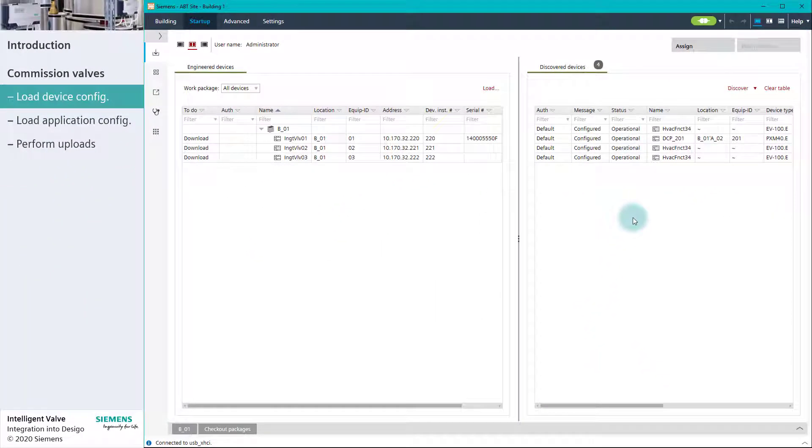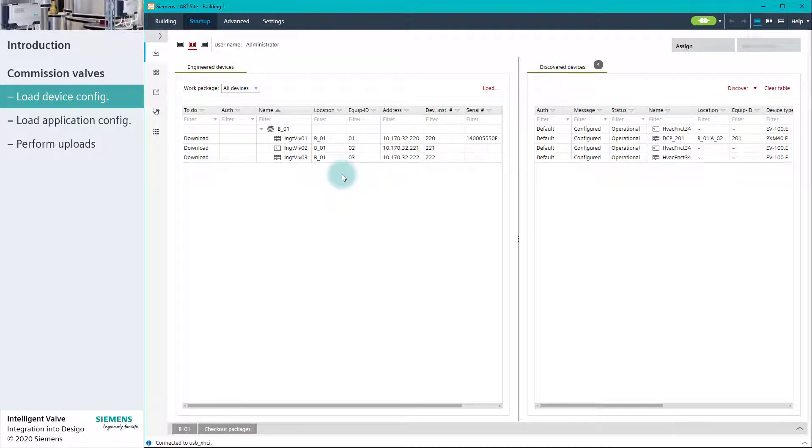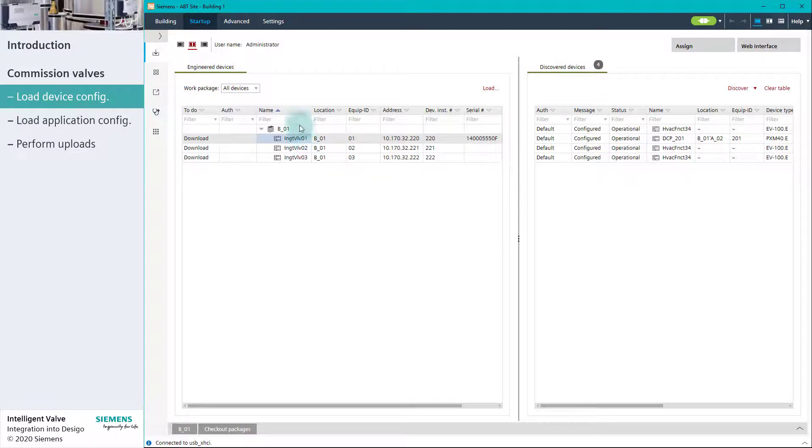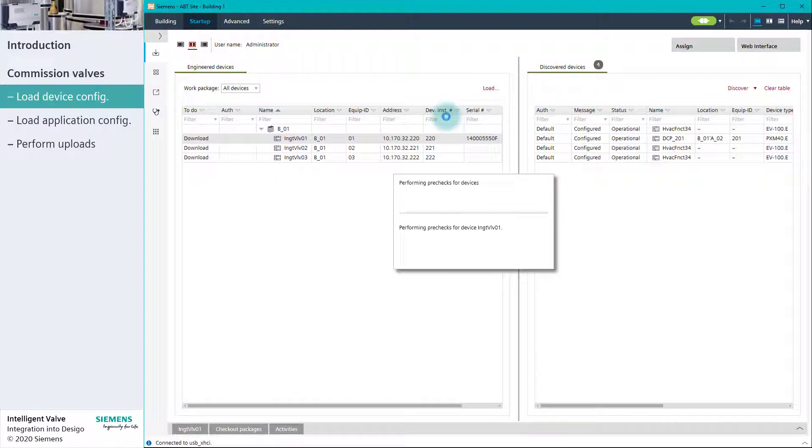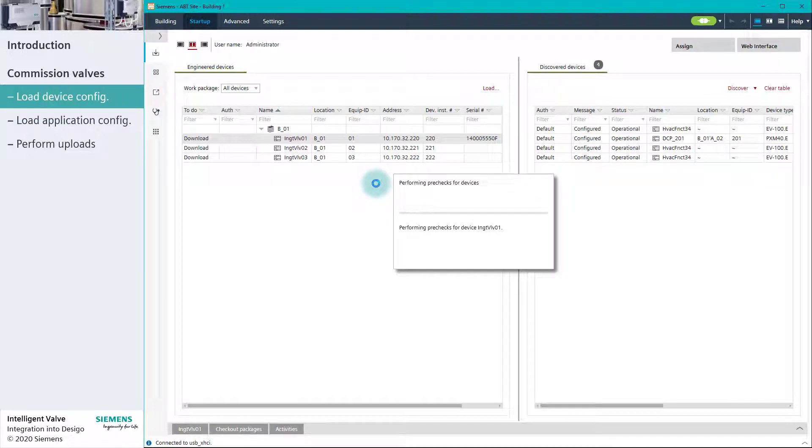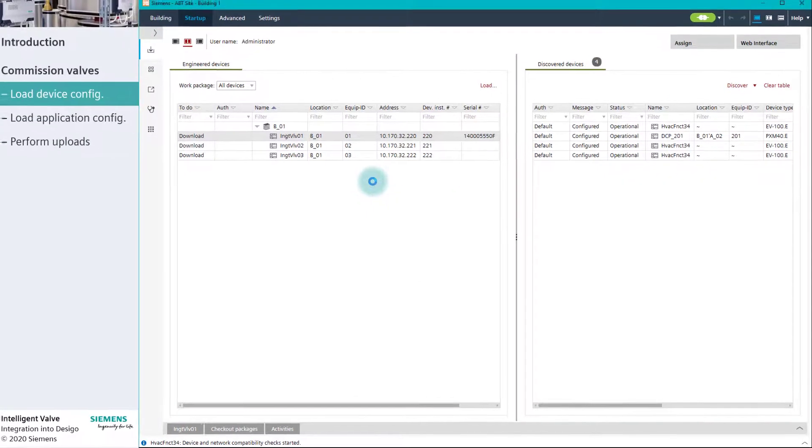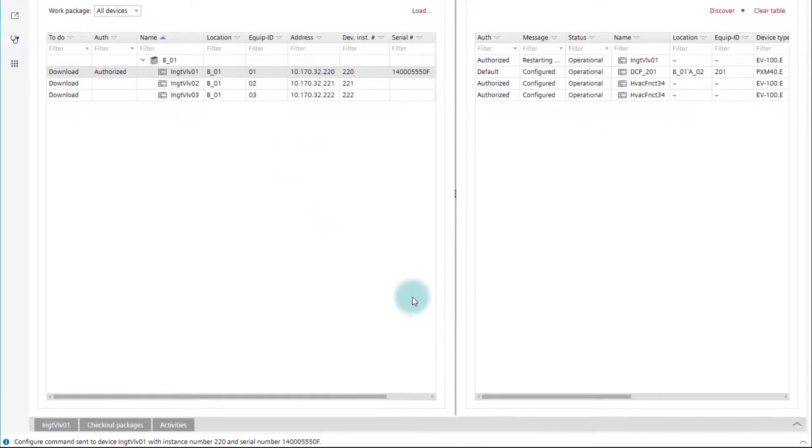We are now going to download the device network configurations to the discovered intelligent valves. This can be achieved in several ways. One way is by having the serial numbers pre-engineered in the serial number field, and then downloading the device network configuration by clicking on the device network configuration option from the Load menu. The user profile is validated, and then the device is configured and restarted. We can check the progress in the Log tab below.